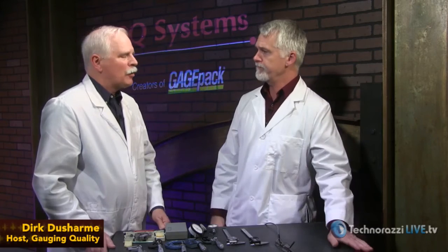We didn't talk about accreditation. Correct. Lab accreditation is something that a lot of customers will be considering when they're choosing a calibration lab. The accreditation process is a very good process. It looks at all forms of the calibration business. Are we talking 17025? 17025 is the typical one. There are others, but that's the one most labs will be accredited to. A lot of the labs take the accreditation very seriously, and they put a lot of effort into making sure they're running within the parameters. There are unscrupulous ones that put all their time and effort into just passing the audit. So it's not a guarantee of a good lab, but it's a very good indication of it.